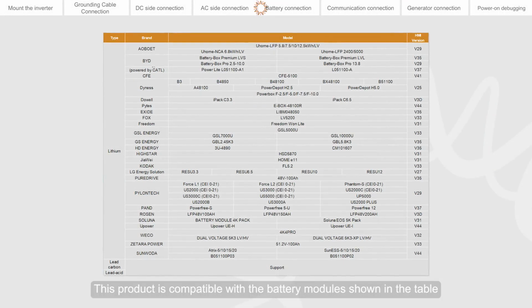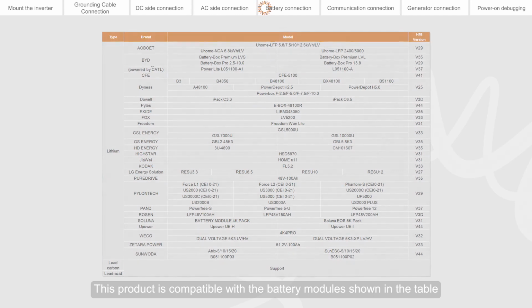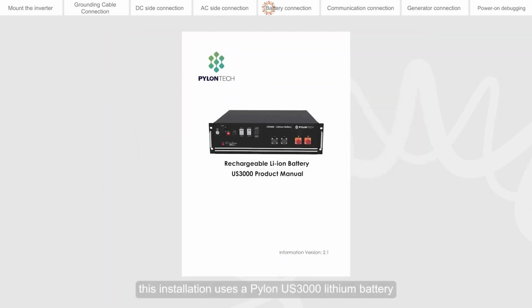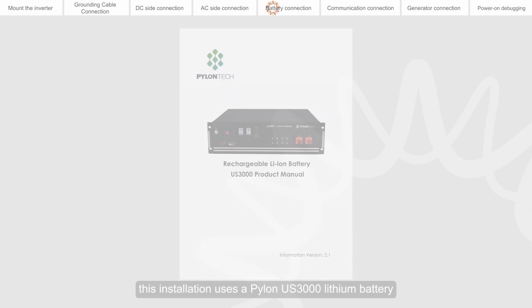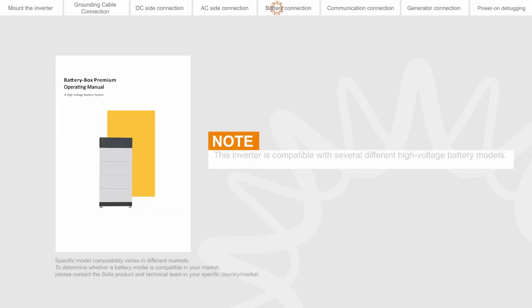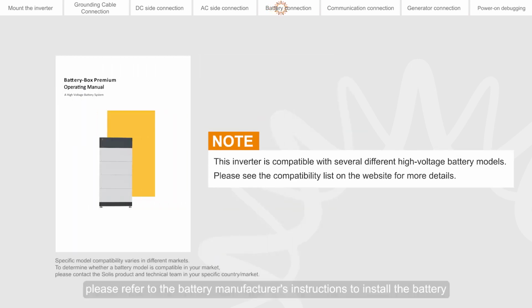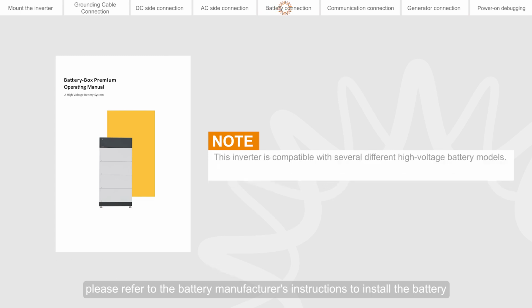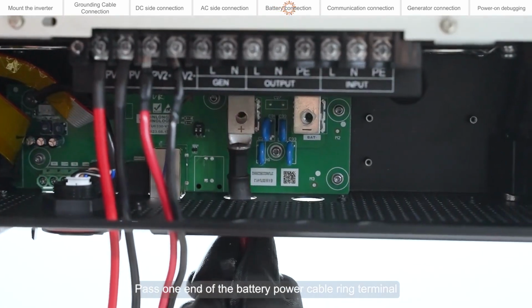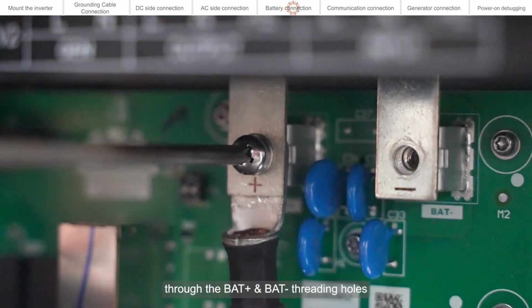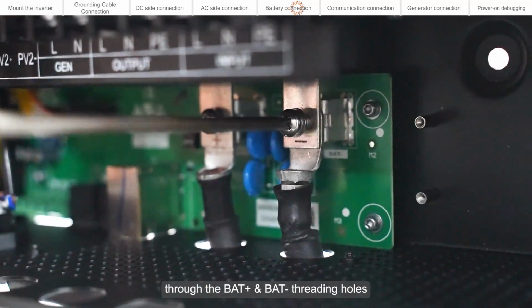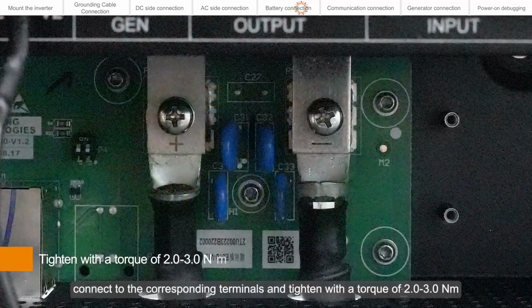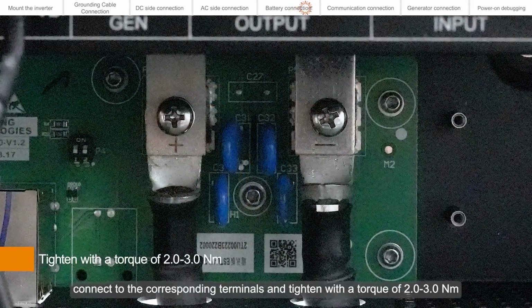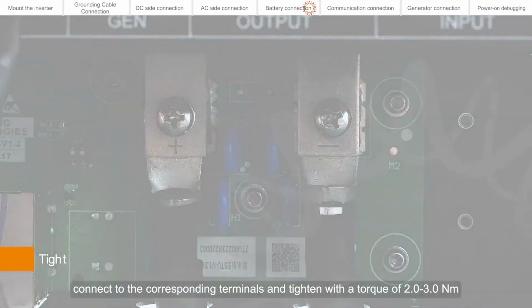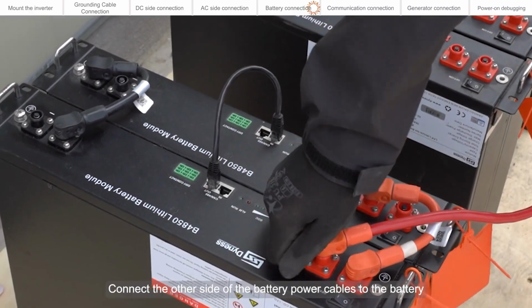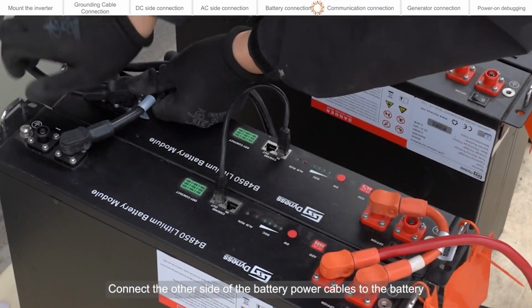This product is compatible with the battery modules shown in the table. This installation uses a Pylon-US 3000 lithium battery. For battery installation, please refer to the battery manufacturer's instructions. Pass one end of the battery power cable ring terminal through the BAT+ and BAT- threading holes. Connect to the corresponding terminals and tighten with a torque of 2.0 to 3 newton meters. Connect the other side of the battery power cables to the battery.